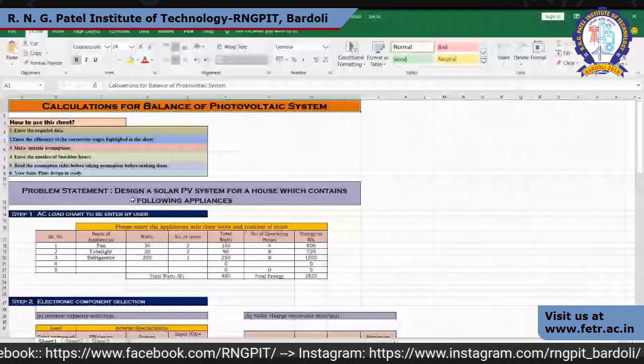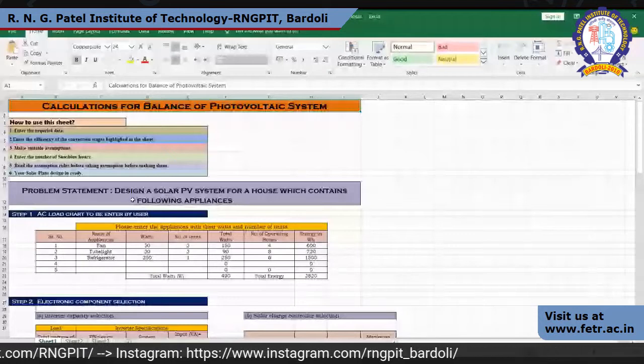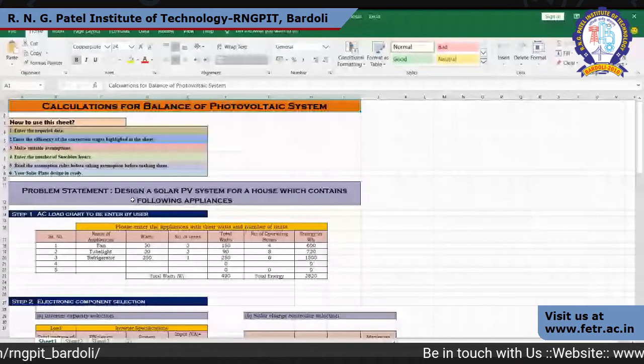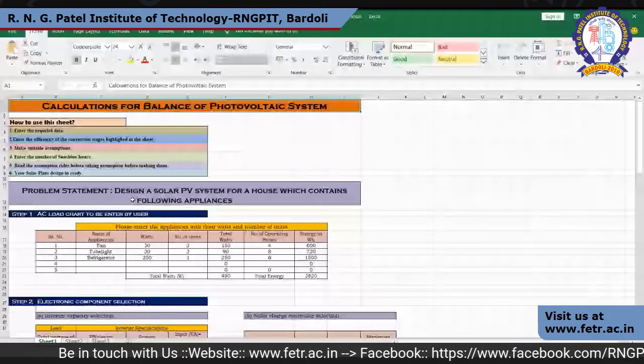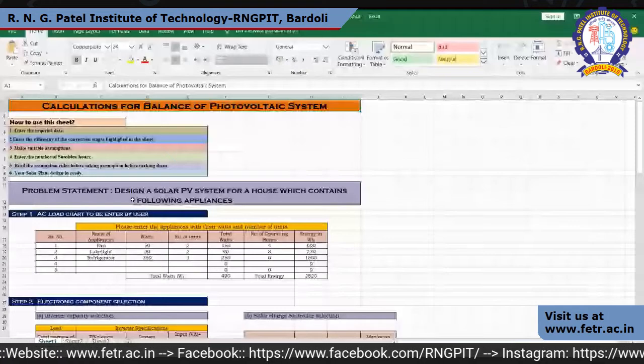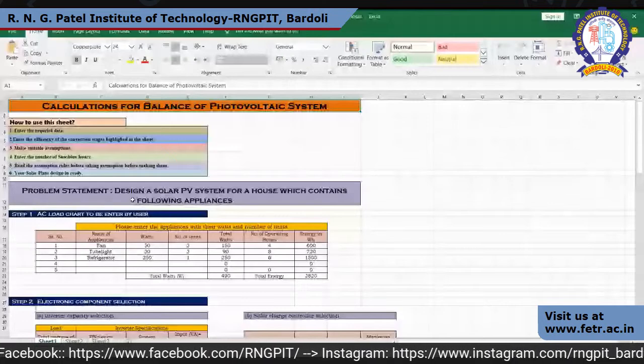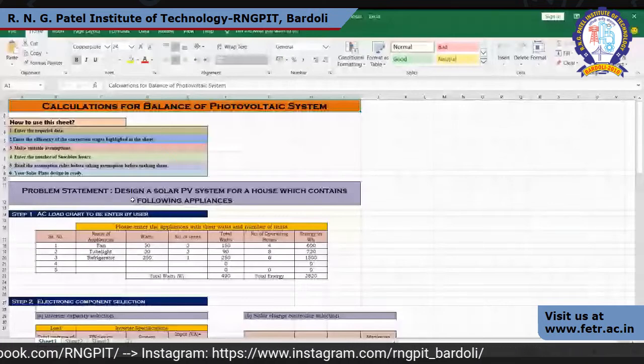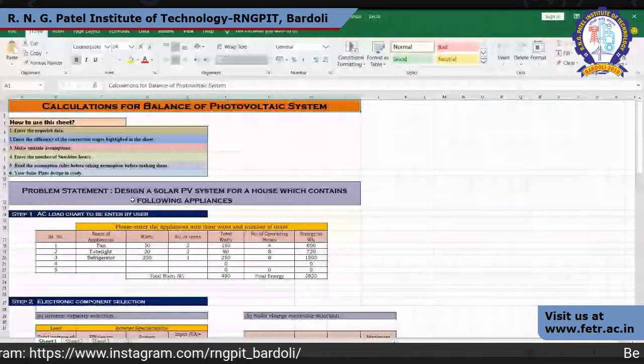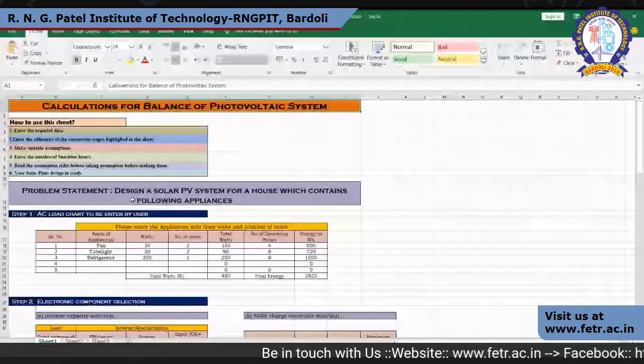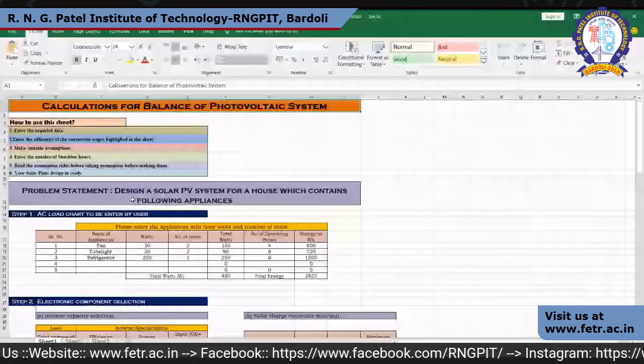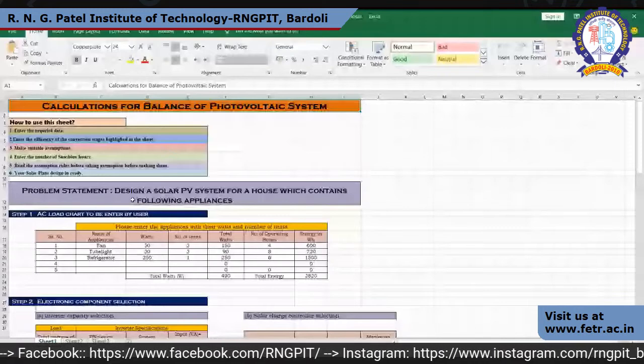Then we'll go with SPV sizing, starting with energy calculation. We are considering 95% efficiency for the battery. Again, the battery will get 3229 energy from the SPV. We are assuming only 4.5 hours of daily sunlight for effective power output. There is a cap here; you may assume 6 or 7 hours, depending on that, and your SPV module voltage will change. So this is 718, and we are designing an 800 watt system.